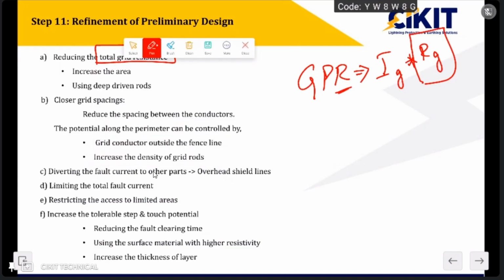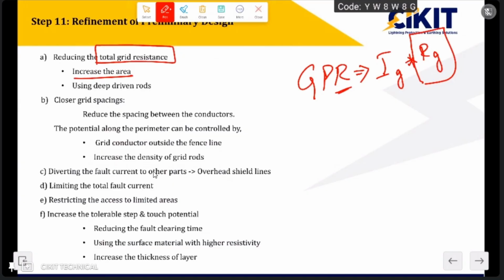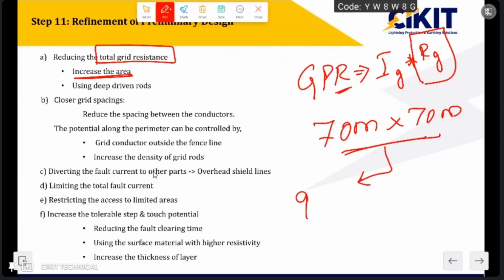The total grid resistance can be reduced by two methods. The first method is increasing the area. For example, in the initial design, I have considered 70 meter cross 70 meter. If the value is still higher, then what can we do? We can increase the area from 70 meter to 90 meter.